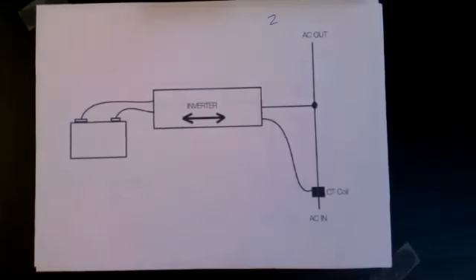It doesn't have a separate charging circuit. It has the same inverter. So basically, if I look at certain inverters, and I'll use, for example, a lot of the Axpert inverters, they will have a charger inside the inverter and they'll have an inverter. Ours is the same device. The whole inverter reverses. That means it can't charge the battery and discharge at the same time. It can only do one or the other.